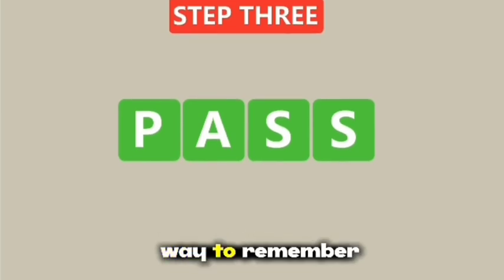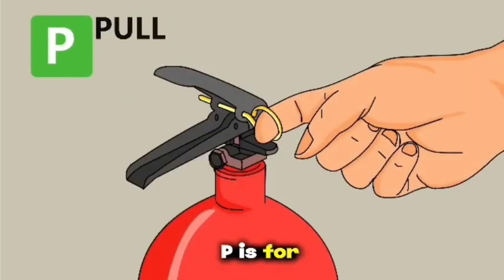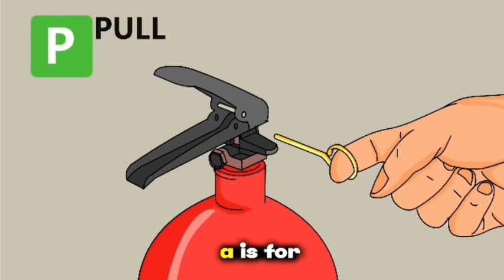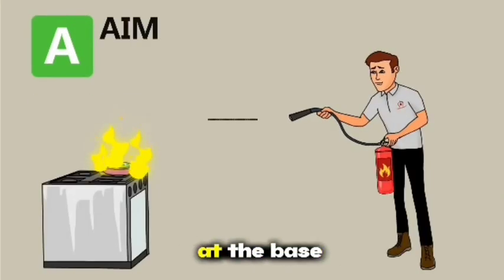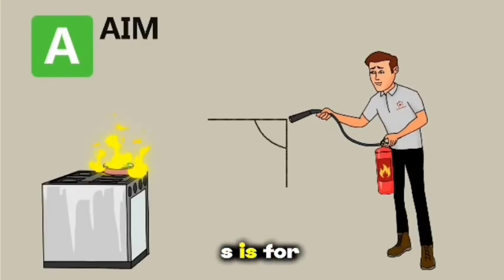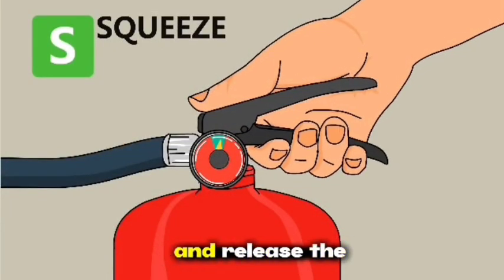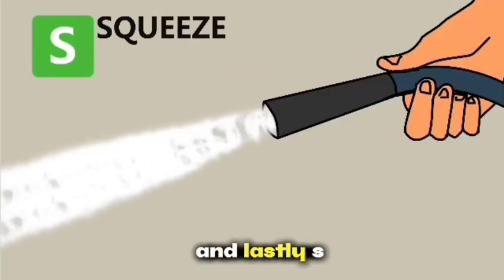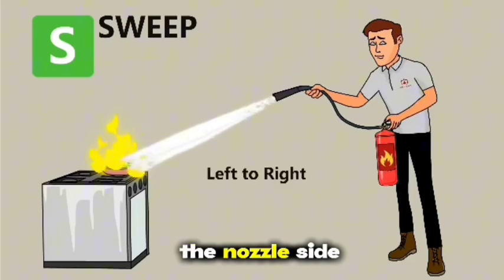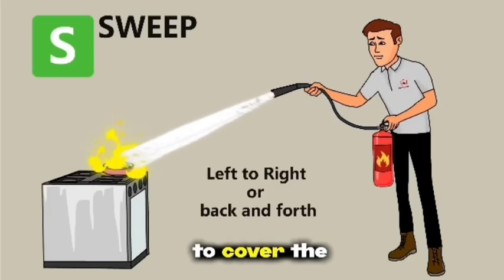The PASS technique is a simple way to remember the process. P is for pull the safety pin, A is for aim the nozzle at the base of the fire, S is for squeeze the handle and release the agent, and lastly S is for sweep the nozzle side to side to cover the area of fire.